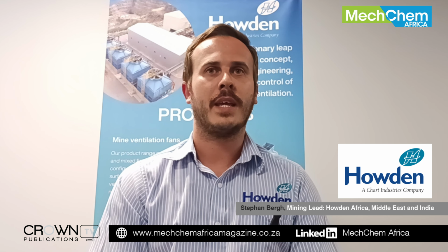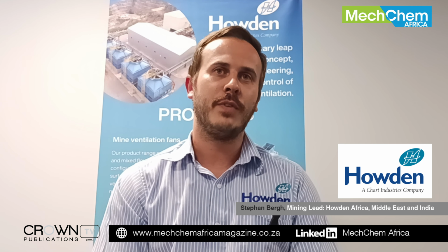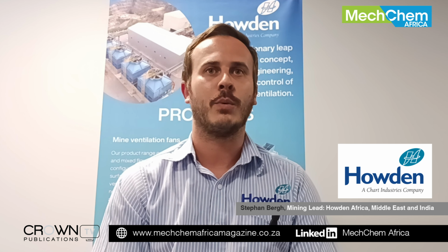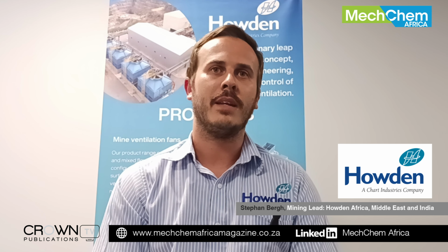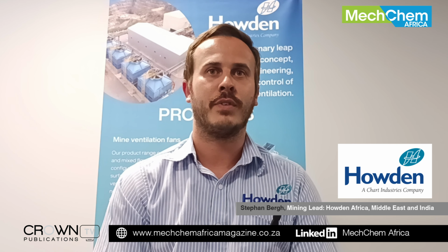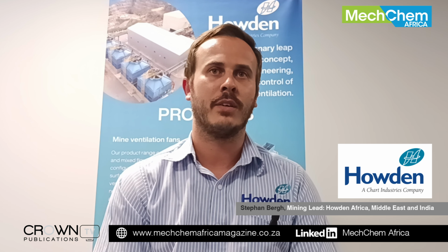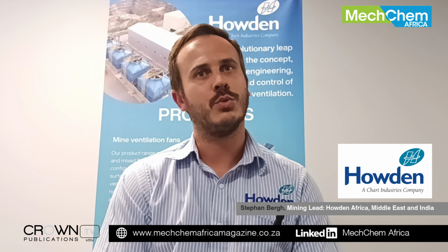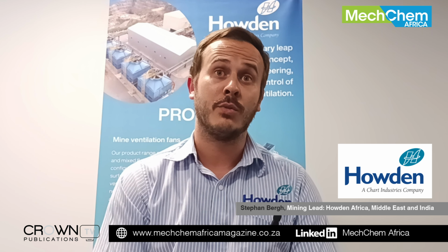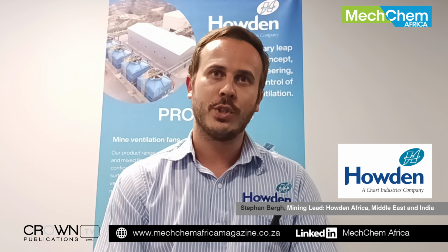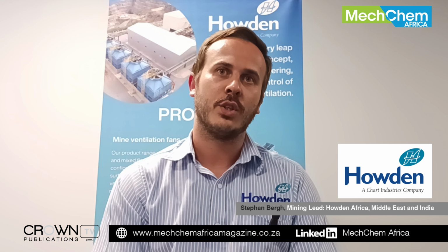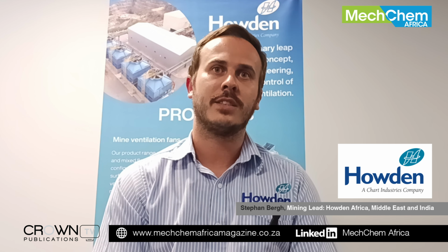Level 3 is flow and gas sensor integration. It's where the feedback from the sensors underground communicates with the software. The software then, based on the level of gases, temperature, etc. underground, communicates with the hardware in turn: VFDs, remote IOs, actuators on regulators. The software computes and calculates the air demand, communicates with those pieces of hardware, and then adjusts them in accordance with the conditions underground.